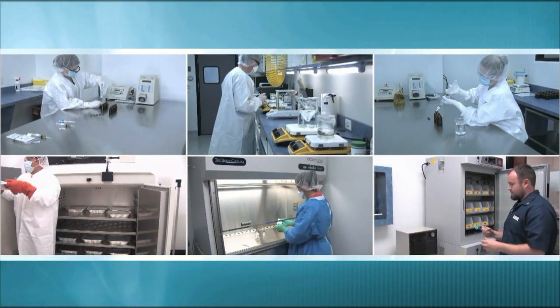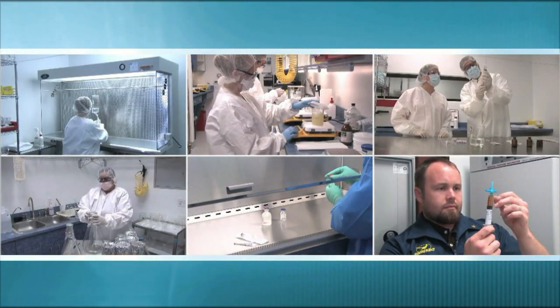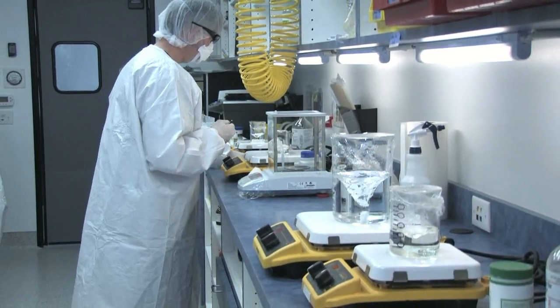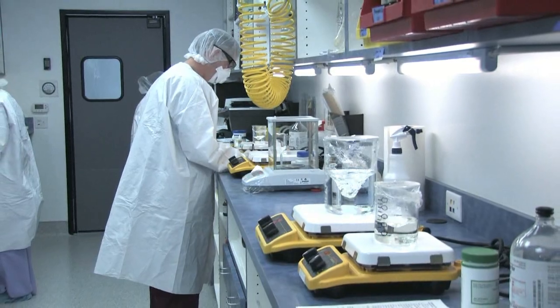The walls in these rooms have a non-porous surface with an epoxy coating and are cleaned routinely and environmentally tested under strict guidelines. This entire facility is maintained at a constant 68 degrees, with an air particle count maintained at an acceptable level by continuously running HEPA filters.